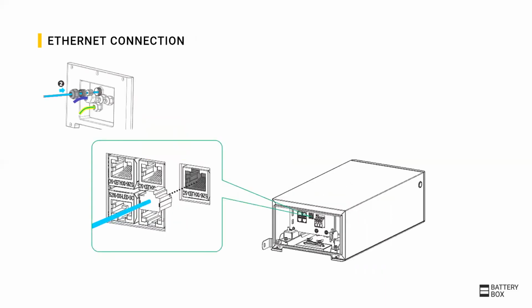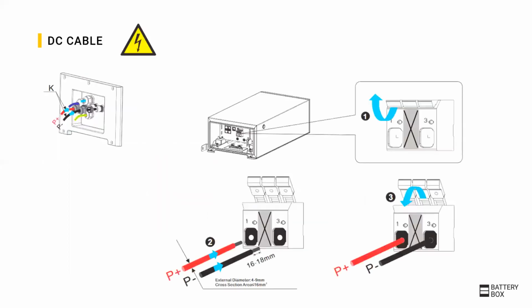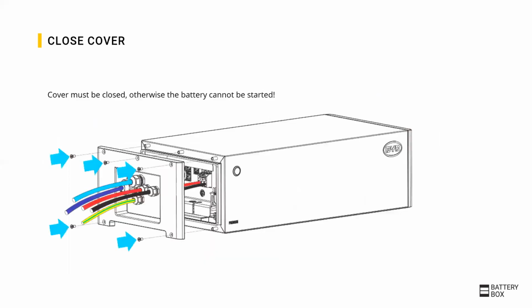Next is an Ethernet cable to establish an internet connection. It is optional, but we highly recommend it to allow for remote updates and remote service. The DC cable connection is shown here. You can see the DC cables, and you can use DC cables with up to 16 square millimeters. After connecting all cables, close the cover. The battery cannot be started if the cover is not closed correctly.